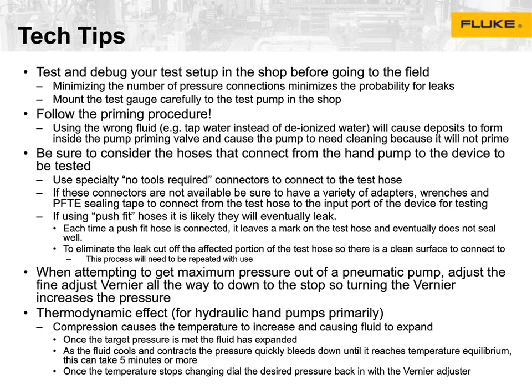Last but not least, we'll talk a little bit about the tech tips here. This is sort of a wall of text. A lot of this is common sense, but the reason it keeps being repeated is that it isn't that common. Test and debug your setup before going into the field. Keep your hoses as few as possible and as few connections as possible. If you can, test your pump carefully or mount your gauge on the pump in the shop. Don't try to do it in the field where conditions are not ideal. Follow the priming procedures. I've already said it once. I will say it again before the end of this presentation, but using the wrong fluid is very bad and will cause you a lot more work than you need to.